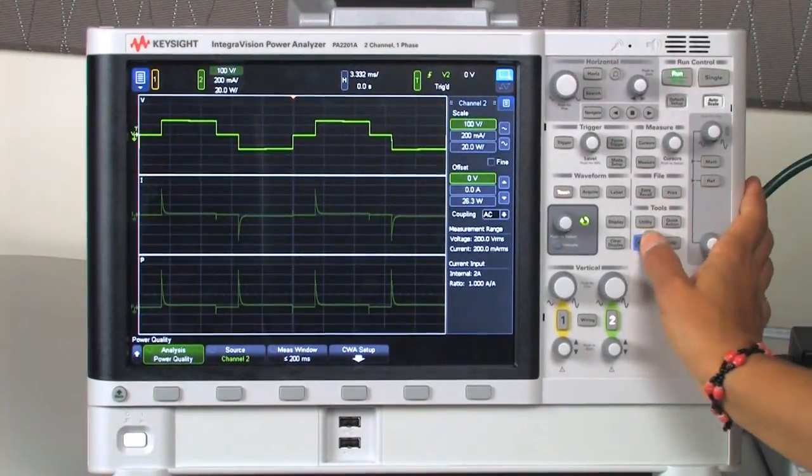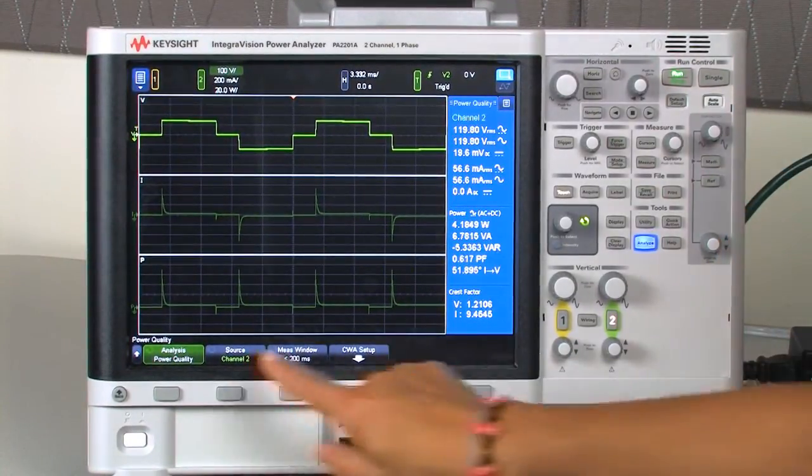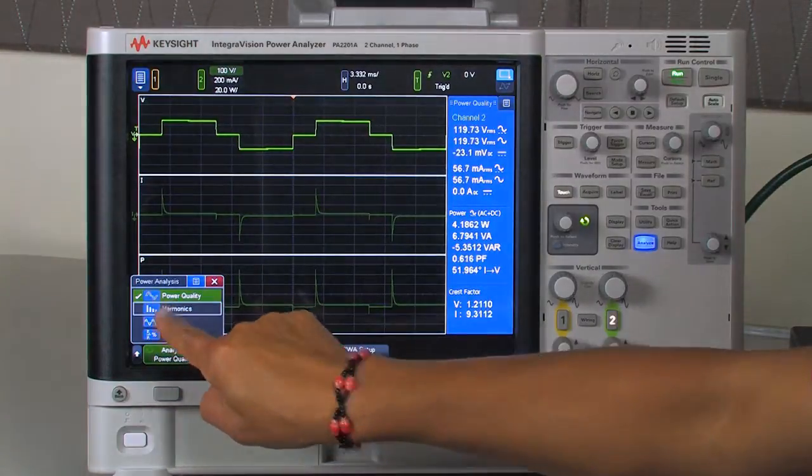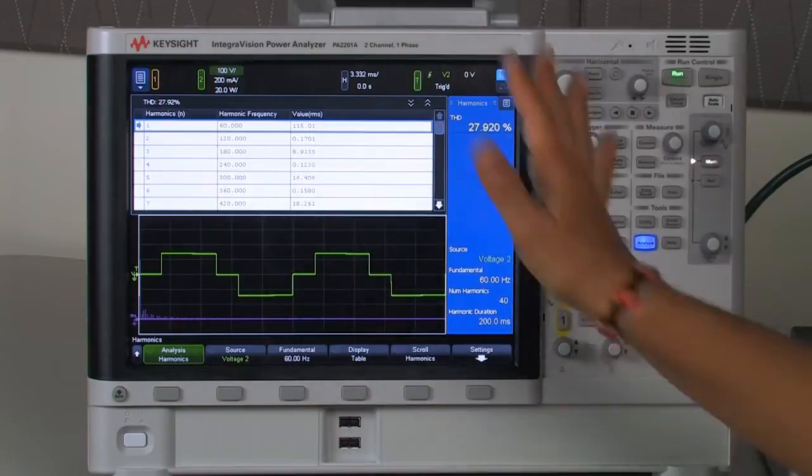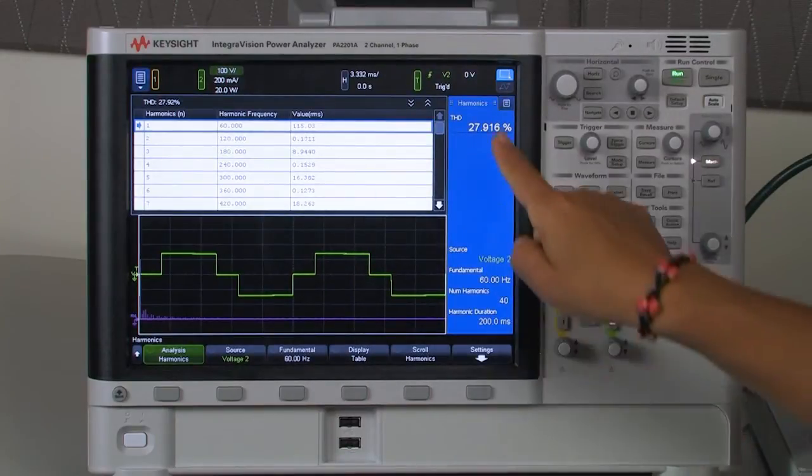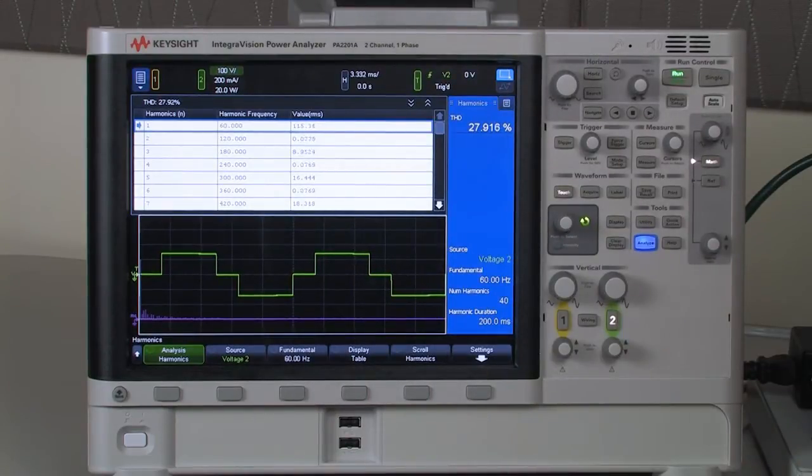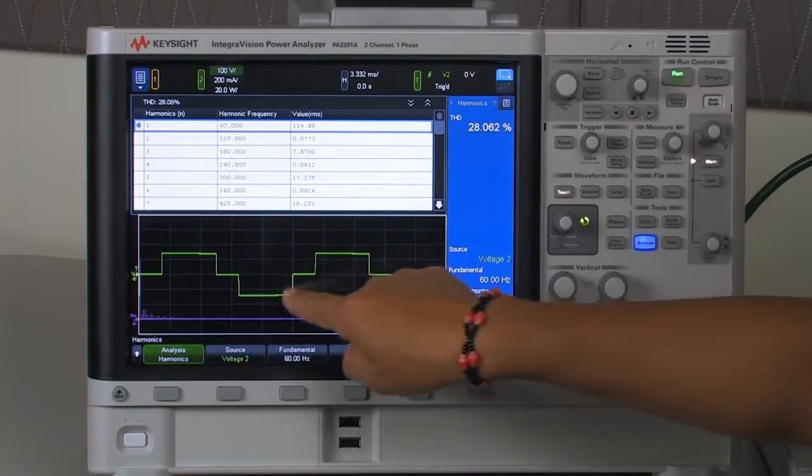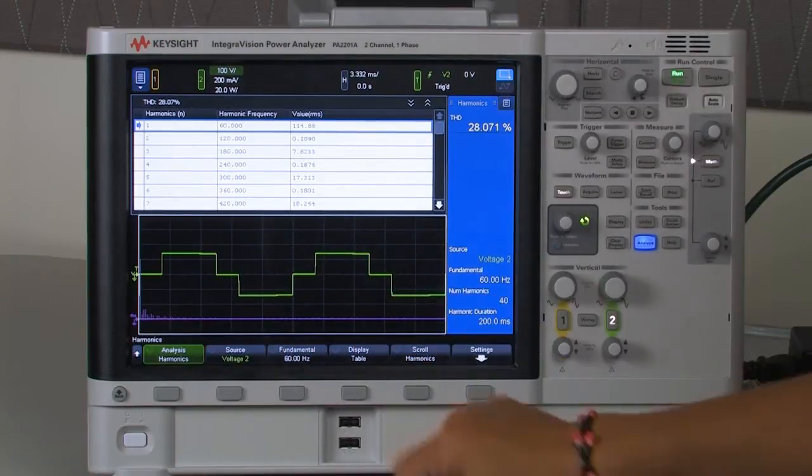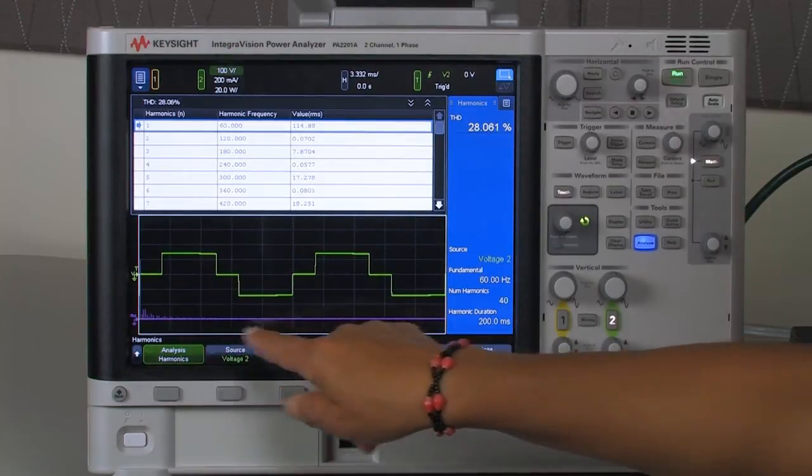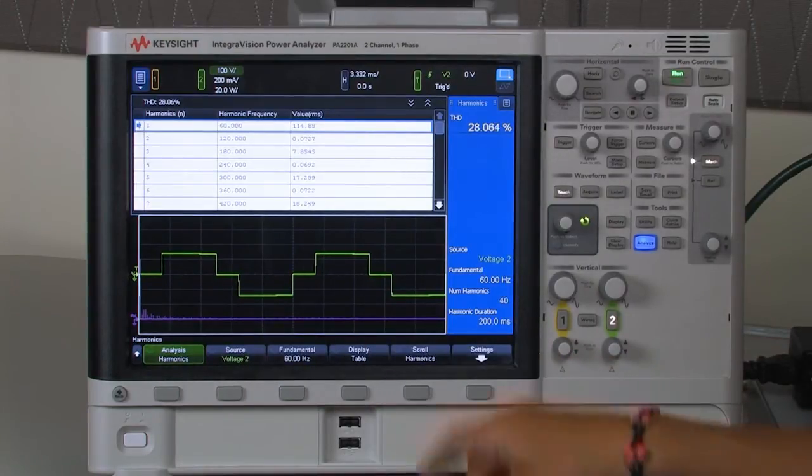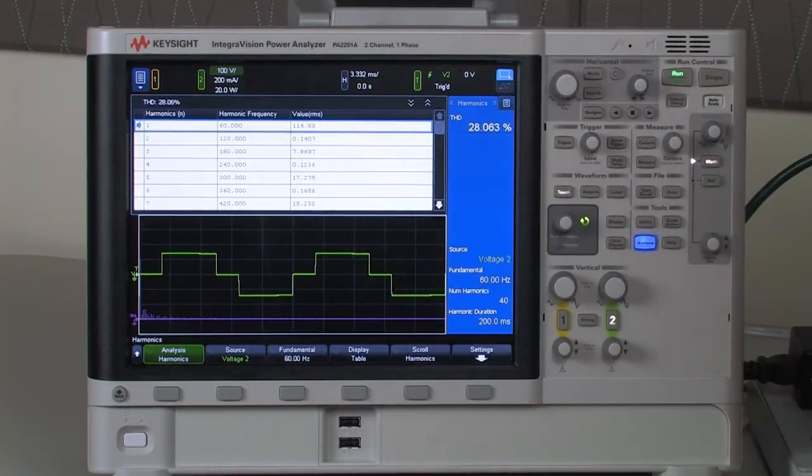So all I need to do now is push the Analyze button and from the menu I pick Harmonics. Quickly I can evaluate that my harmonic distortion on voltage is about 28%. At the same time I can observe the signal itself in time domain. I also see DFT on the proper line and I have the values of each harmonic in the table.